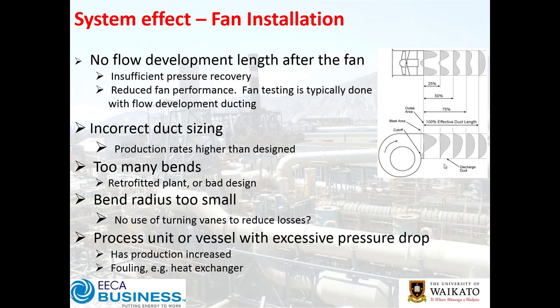It's critical to select the right fan and get the right duct installation and sizing to gain these efficiencies; otherwise these are additional losses. Too many bends can be a problem. For most of us using existing plant, we've inherited the sins of the past — it's very difficult to rip everything out, and buildings are locked in with space constraints. There are important strategies with flow control guide vanes to improve airflow in these situations and recover some of these losses.